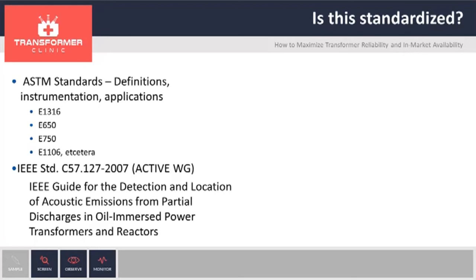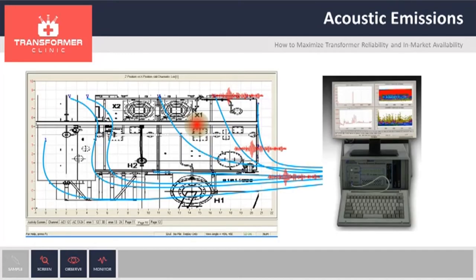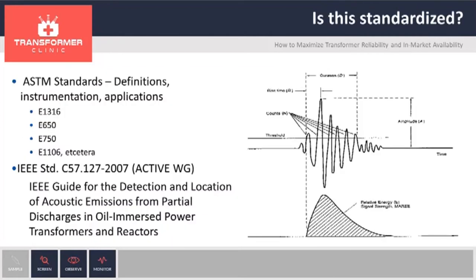We put up to 24 sensors on the transformers. For every single sensor, we actually collect a lot of features. We call them acoustic emission features, such as duration, energy, amplitude, number of counts, et cetera. This information is used to characterize different defects. You might have an electrical fault, a high temperature fault, or a mechanical defect. They have different features, and that's how we can characterize them.